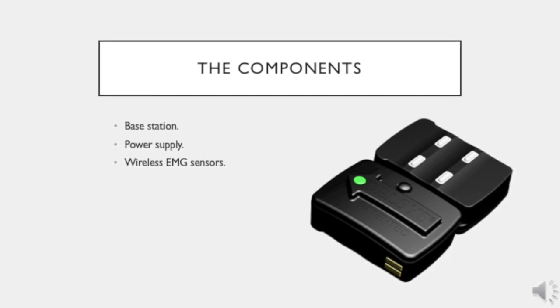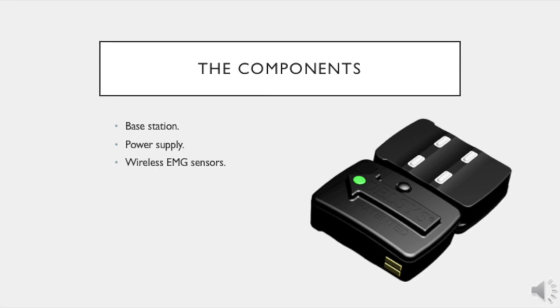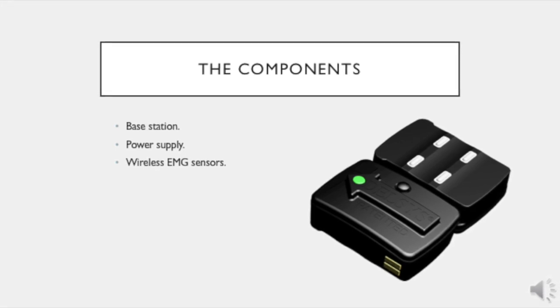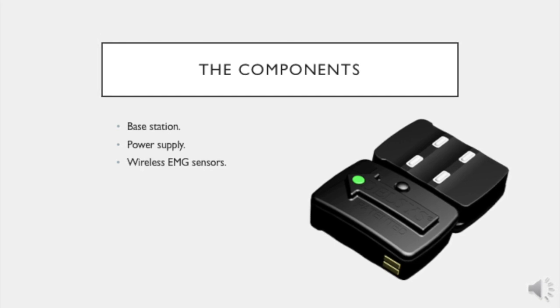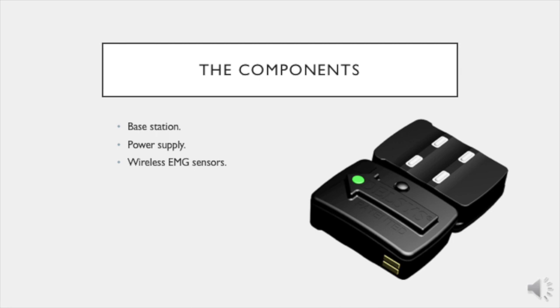The arrow on the EMG sensor indicates the orientation of the contacts on the sensor. The contacts are positioned in a series parallel to the arrow. When placing the EMG sensor, the sensor should be orientated over the belly or centroid of the muscle with the arrow parallel to the muscle fiber.